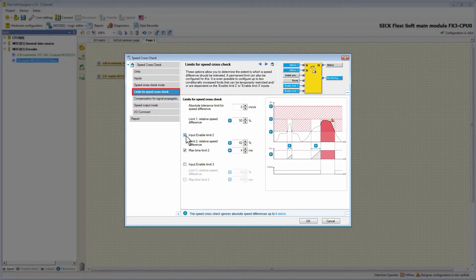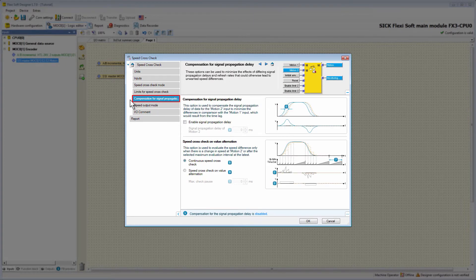Next, we switch to the tab Compensation for Signal Propagation Delay. If one of the two speed signals is transmitted with a delay, for example because of internal evaluation from one encoder, you can check the option Enable Signal Propagation Delay and connect this delayed signal to the Motion 2 input. Then, according to the time you enter in the field Signal Propagation Delay of Motion 2, the speed values on Motion 1 input are delayed during the calculation of the speed difference. In this way, speed differences can be reduced that would otherwise occur due to delayed transmission, particularly on fast changes in speed.